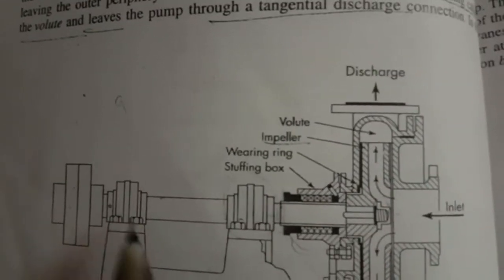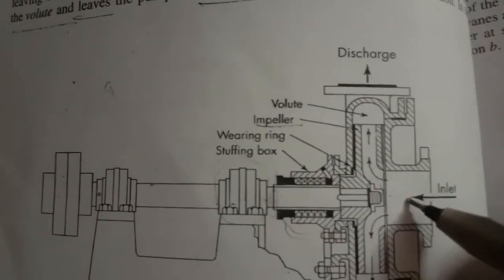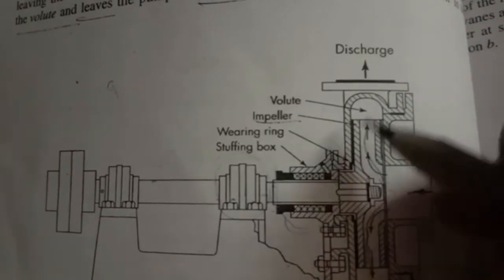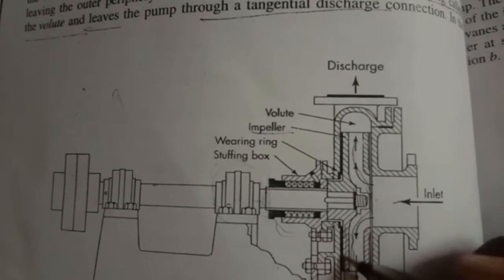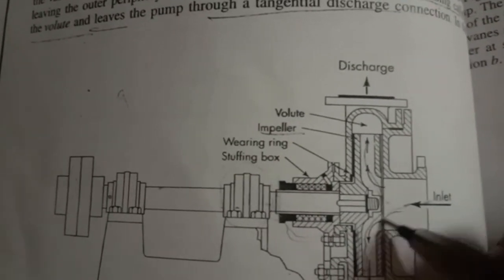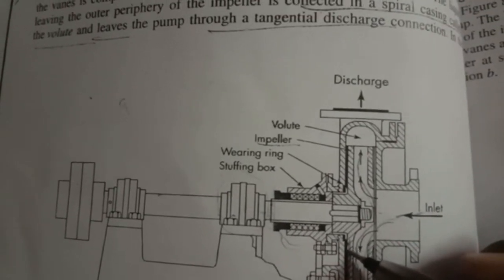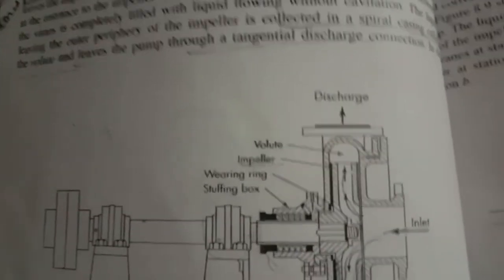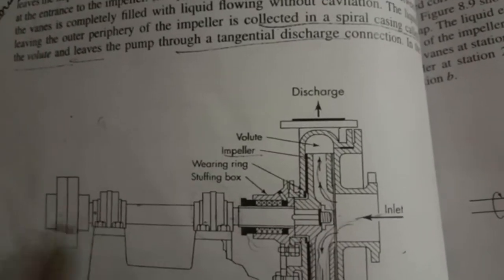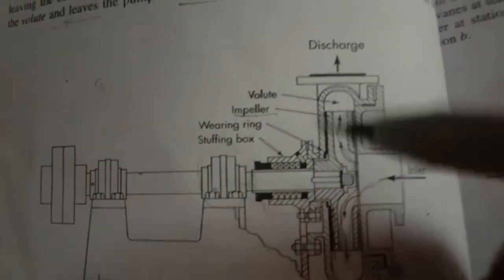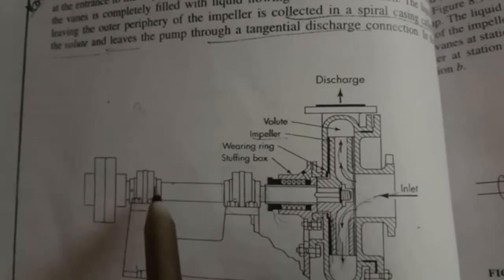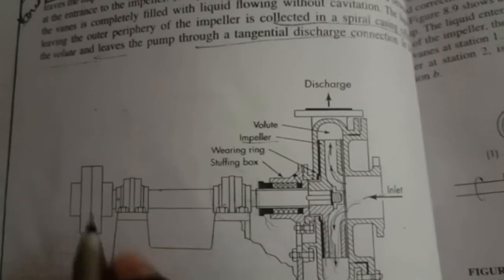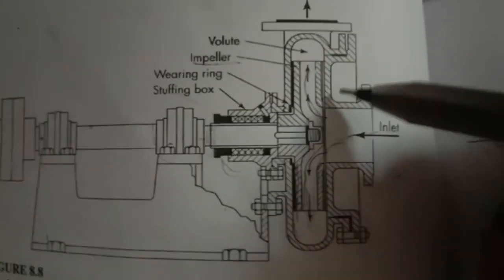In the inlet, we have the first impeller. The impeller will rotate and create centrifugal force. There is a gap, so we have suction at the inlet and we have low pressure on the suction side. We have a large force pushing the impeller toward the suction side, which causes the shaft to move axially. So we have to maintain the thrust bearing to resist this axial force.